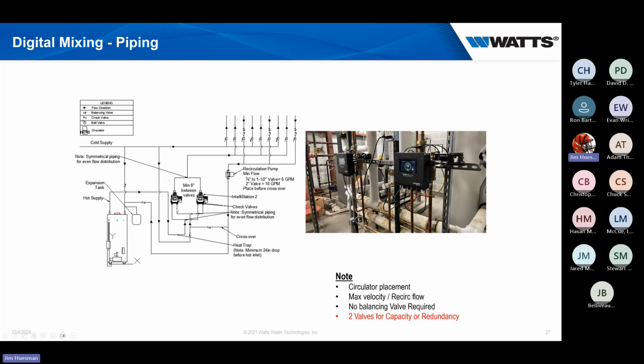We have two different valves, which give us our capacity, but just like everything, it also gives us that redundancy. That way, if I have an issue with one of these valves 5-10 years down the road, I'm not sitting at a senior living center saying this isn't working, we're in big trouble, and now we've got to drop all our heaters down to that 118 and 120 and go back and adjust everything.